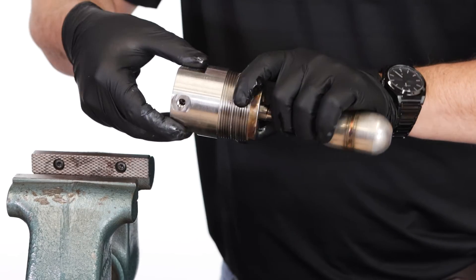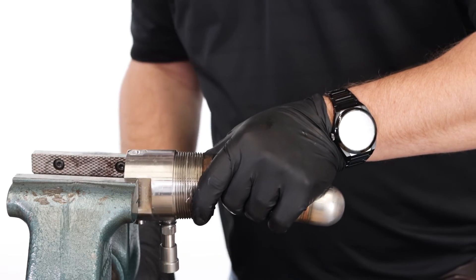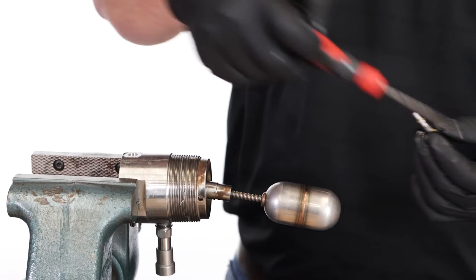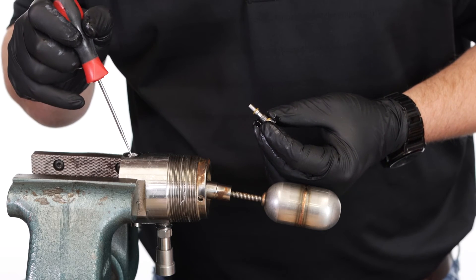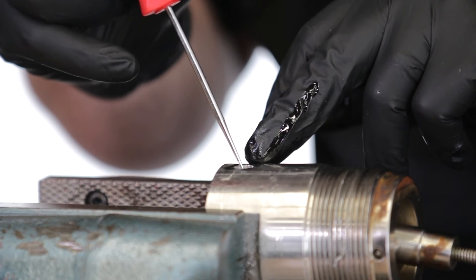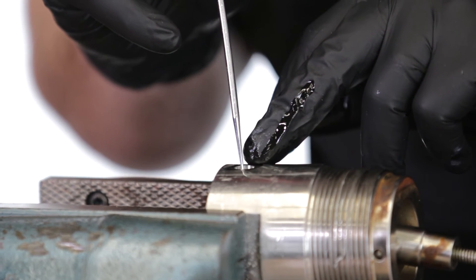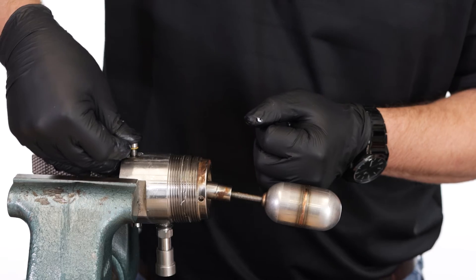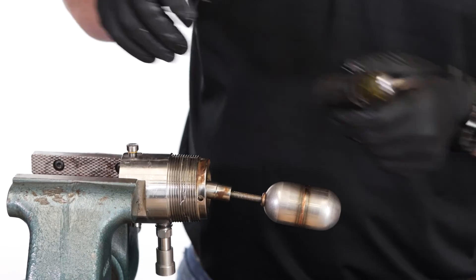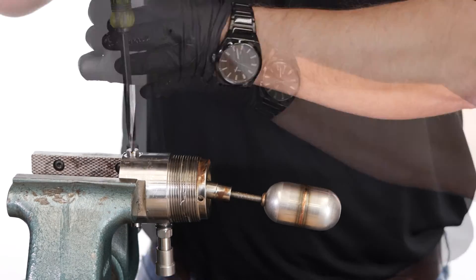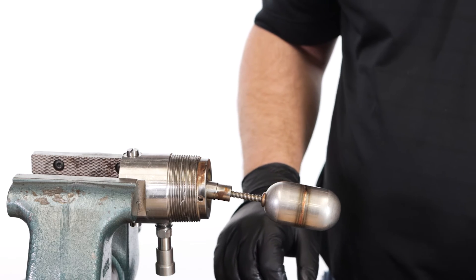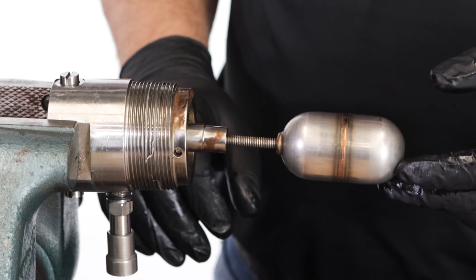Tighten the first seat in place with the flathead screwdriver. Flip the housing around and insert the shuttle. Make sure that the shuttle is fully inserted. Install the second seat and fully tighten it with the screwdriver. If you've installed it correctly, you can hear a faint click sound when the float is moved, telling you that the shuttle can freely move.